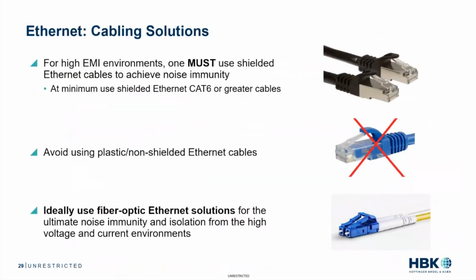In the HBK solution, you have an Ethernet cable that runs between your computer and the power analyzer. And so you want to make sure that the cabling used is not going to have effects from the EMI, the noise. And whenever I get a customer or user that's having maybe an issue every once in a while with the connection between their computer and the power analyzer, I first ask, well, are you using shielded Ethernet cables? So that's the first thing that you really want to consider, is using shielded Ethernet cables, like you see here at the top right, as opposed to what is in the X that's not shielded at all.